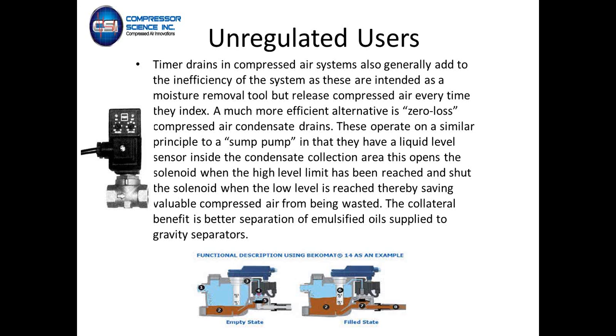The way a zero loss drain works is it works like a sump pump. You've got a limit switch inside of the drain, as you can see in the picture. When the condensate and oil builds up inside the drain, it raises that limit switch and actuates the solenoid. When the solenoid opens to discharge the compressor condensate, it drains the sump down to the low-level switch and shuts the solenoid off before you actually lose any compressed air. These drains are $200 to $300 for a zero-loss drain. If you look at the cost over the course of the year, the paybacks are generally under a year from replacing the timer drains with zero-loss drains.